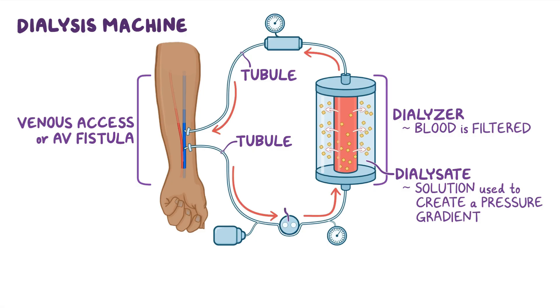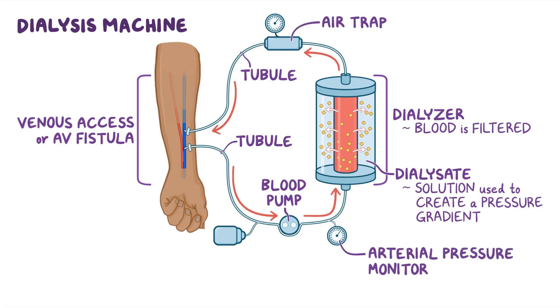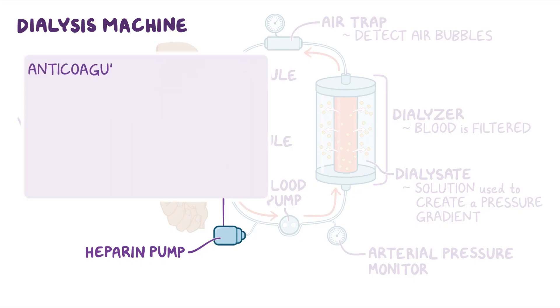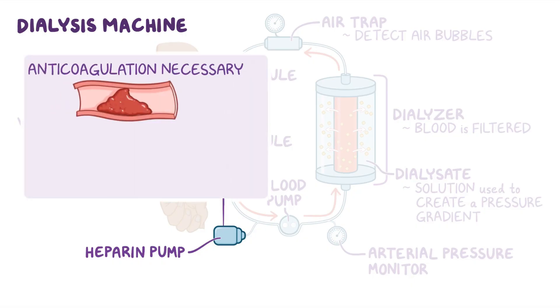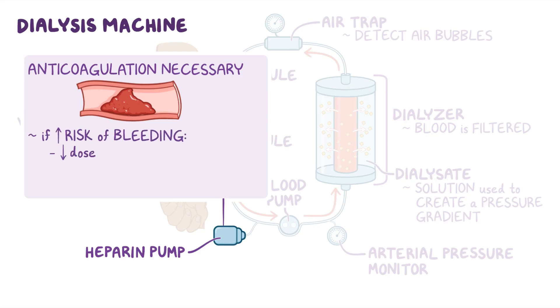Other components include blood pumps to help draw blood from the client, an arterial pressure monitor, and an air trap or sensor to detect air bubbles and stop them from entering the circulation. Finally, the dialysis machine also contains a heparin pump, because anticoagulation is necessary during dialysis due to the risk of blood clots. In clients with a high risk for bleeding, a lower dose of heparin, citrate, or no anticoagulation can be used.